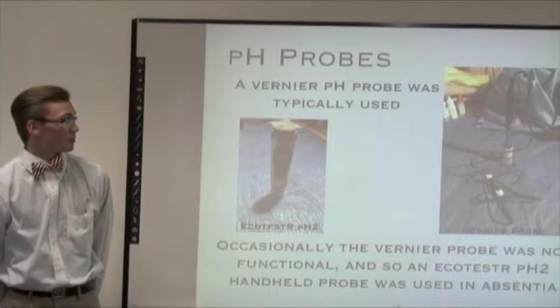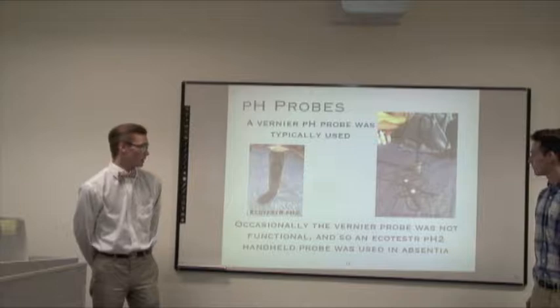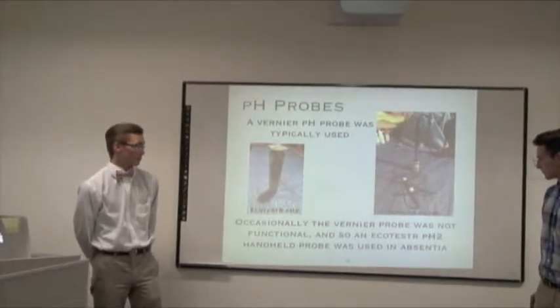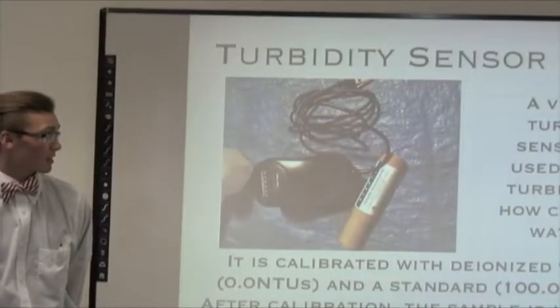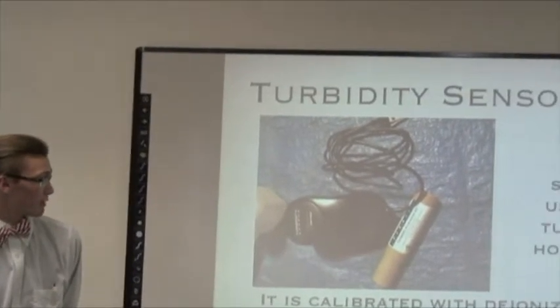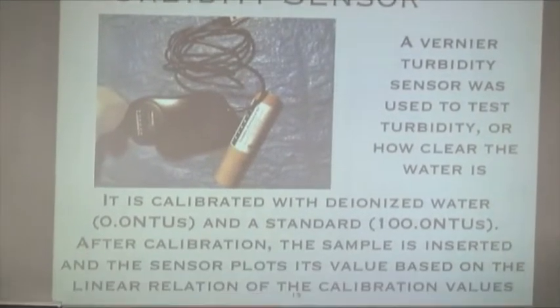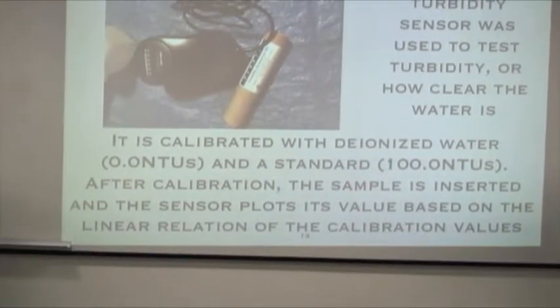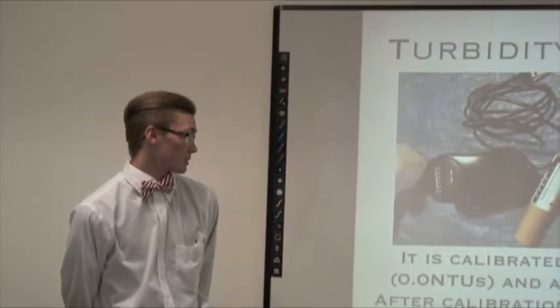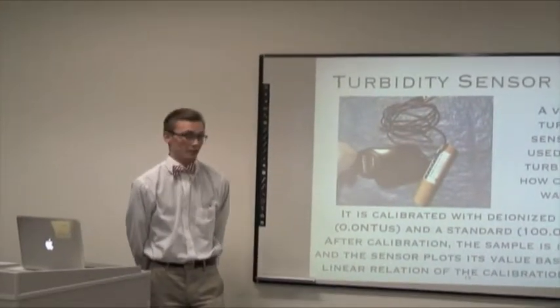For pH we typically used a Vernier probe, but occasionally that was not functional. When that probe was down, we used an Ecotestr pH2 handheld probe. For turbidity — a measure of clarity of the water — we used a Vernier sensor. We calibrated it first with deionized water at 0.0 NTUs and then a standard at 100.0 NTUs. After calibration, the sample is inserted and the sensor plots that value based on the linear relation of the calibration values.